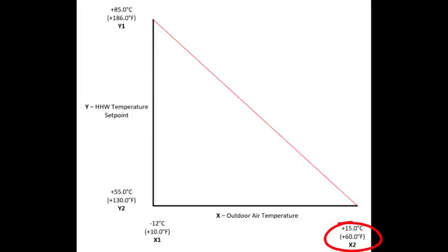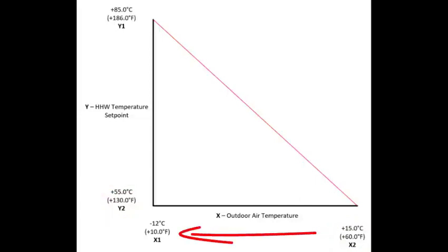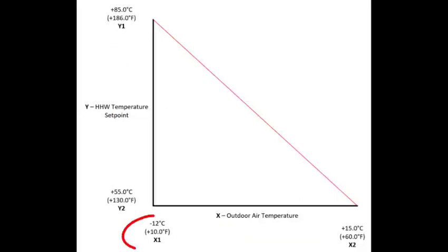In this example, at plus 15, this scale function will return a value of 55 degrees. And as the outdoor air temperature falls, the return value or supply water temperature set point will increase. Once the outdoor air temperature reaches minus 12 degrees Celsius, the supply water temperature set point will be calculated at 85 degrees Celsius.